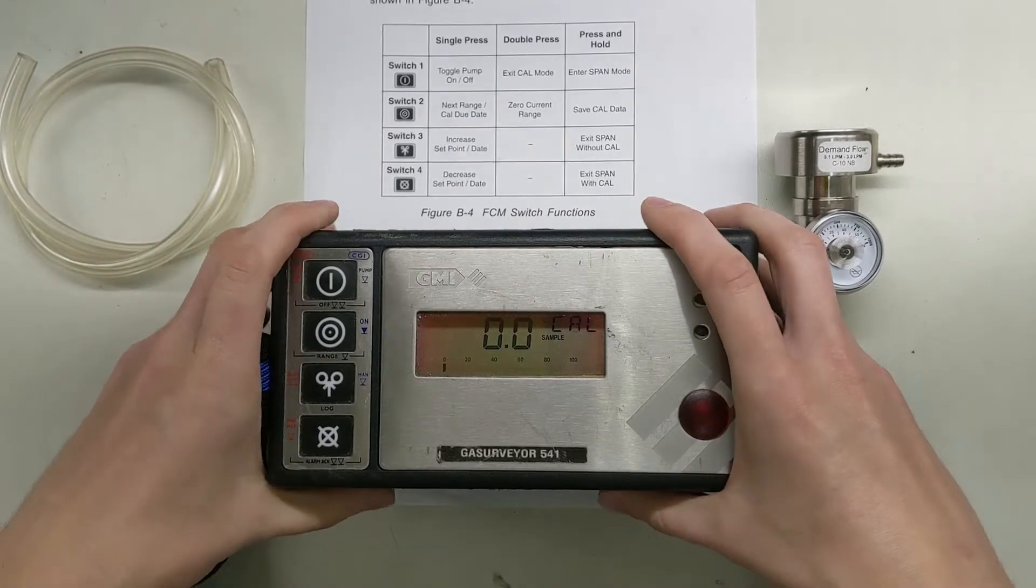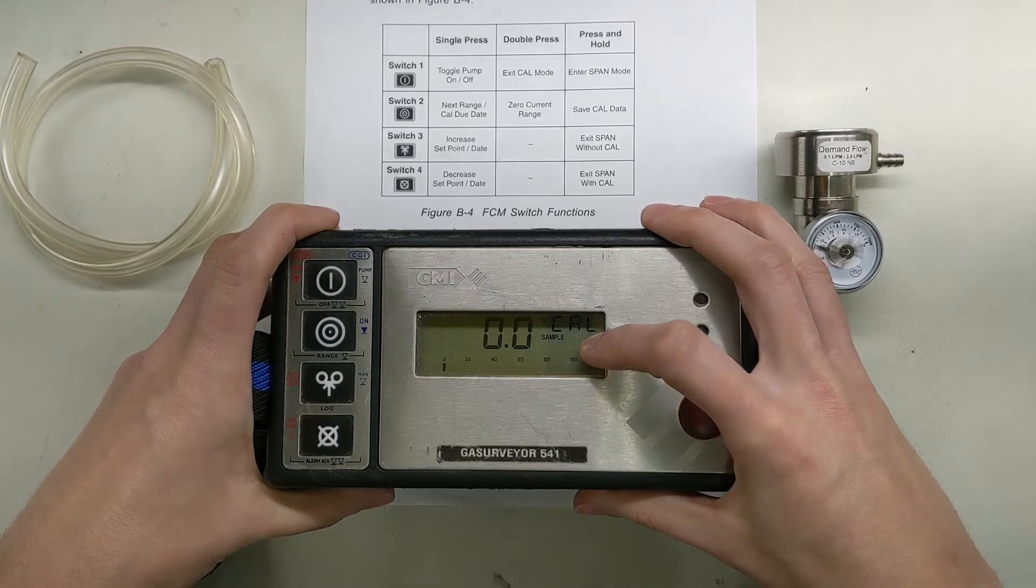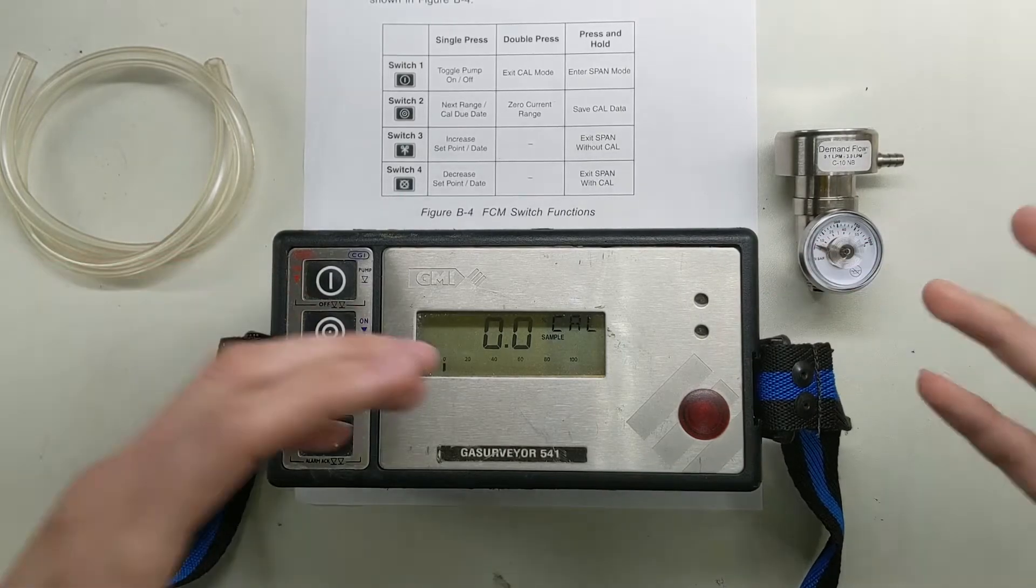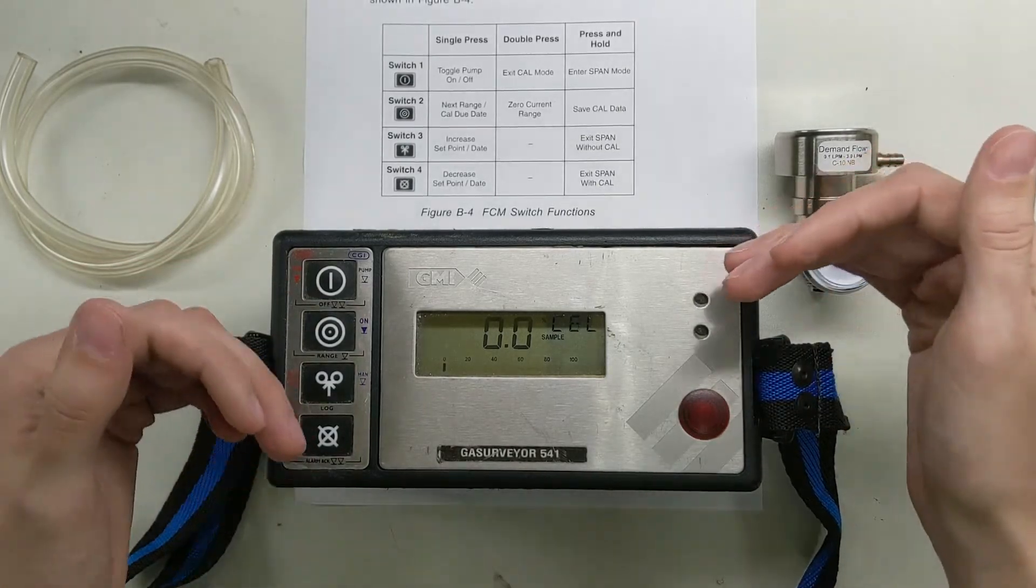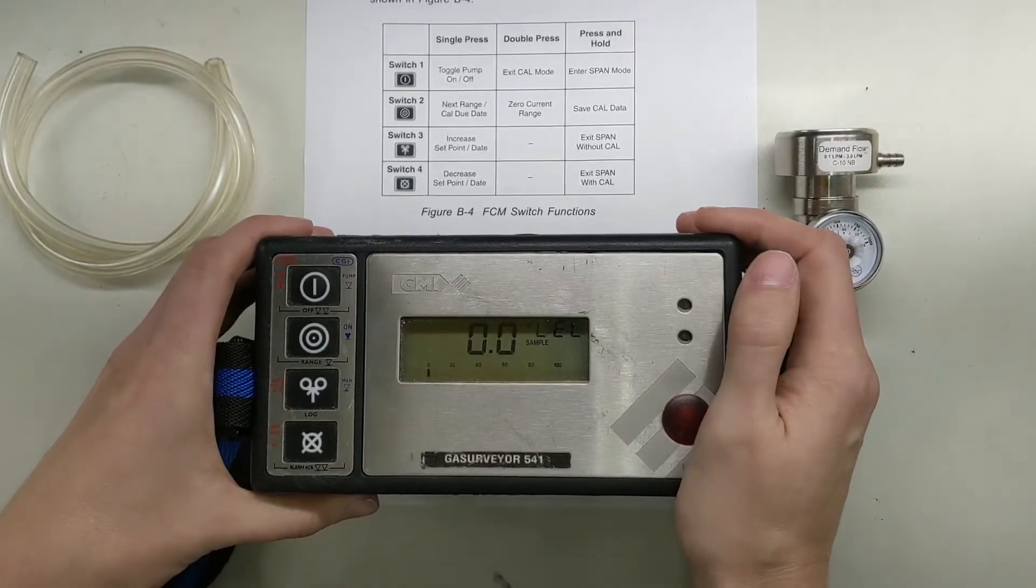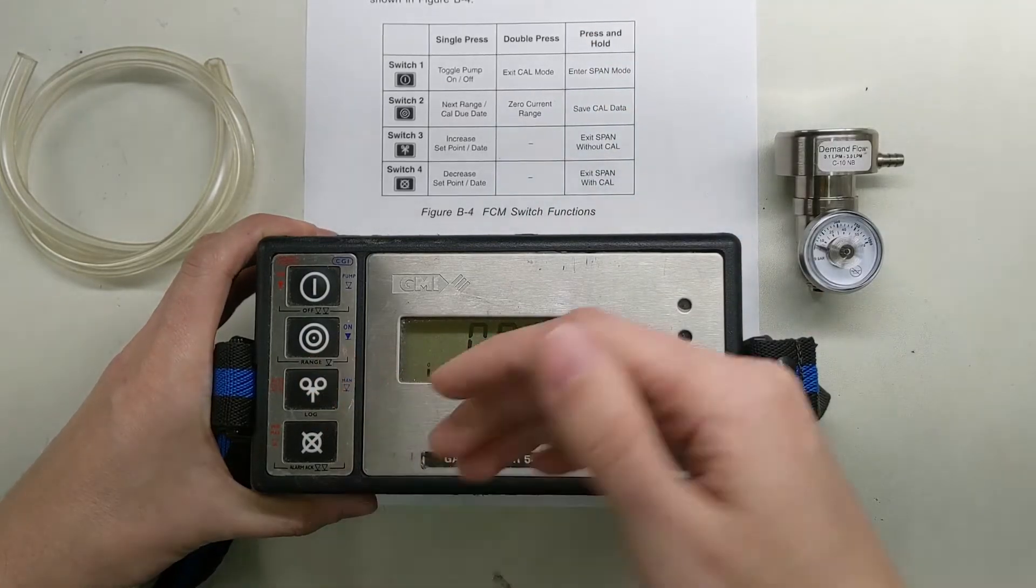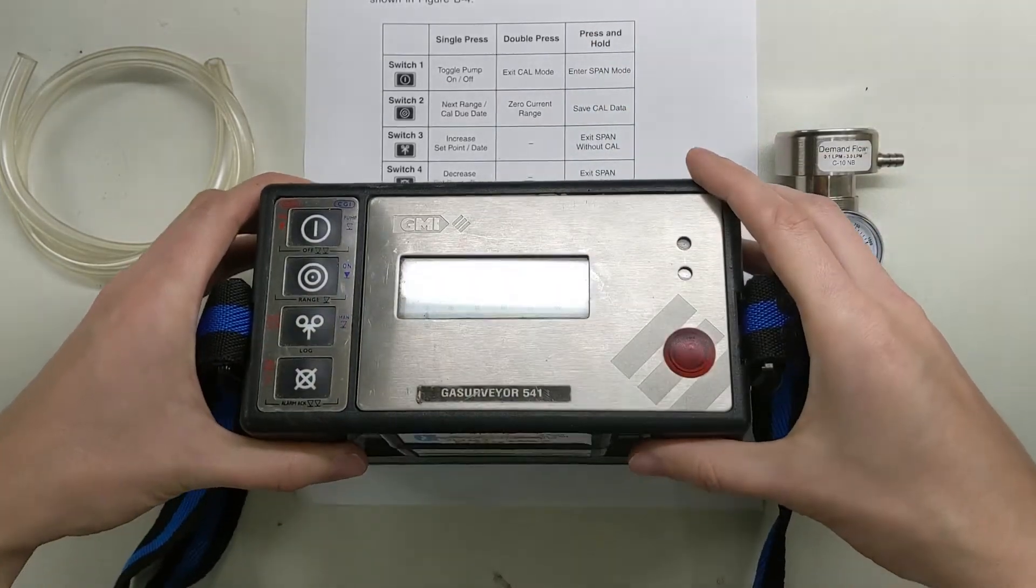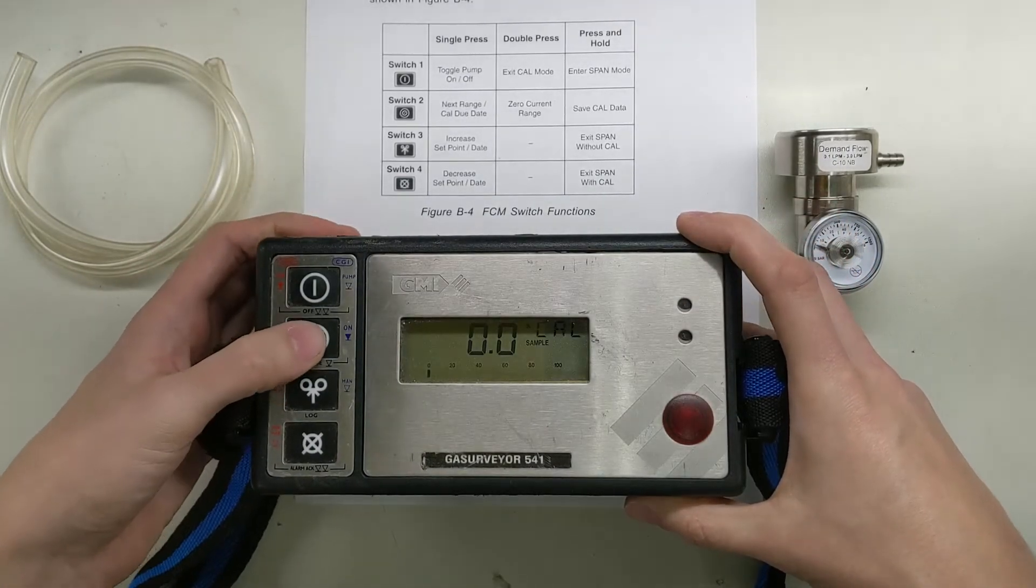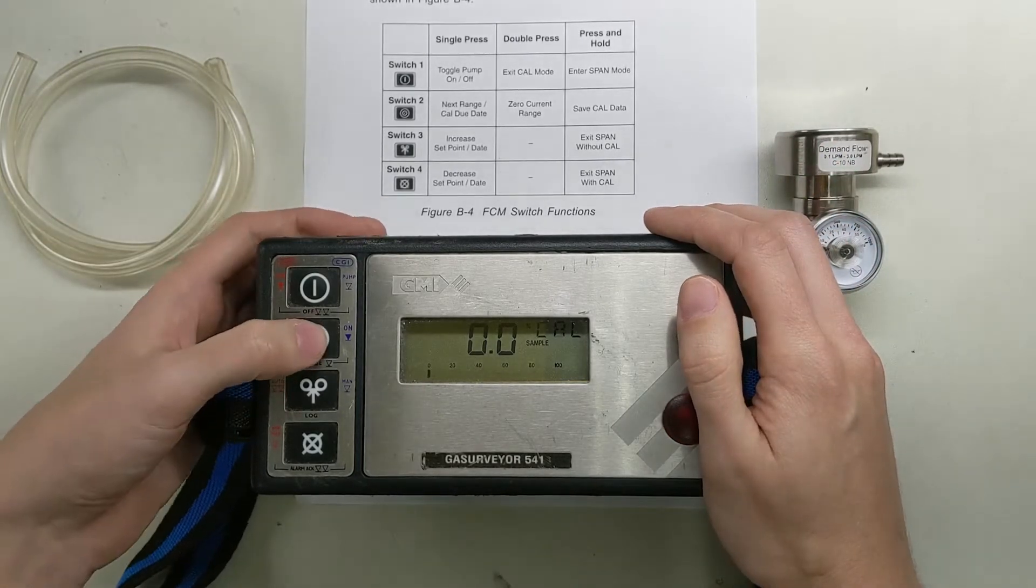First things first, you can see we're in LEL right now. What we're going to do is first we're going to go through and zero each of these with room air. And then I'll come in with the gas cylinders and we'll calibrate each one. If you double press, it's going to zero the current range. If we single press, it's going to move to the next one. So we're going to double tap to zero. Now we've saved a zero there.